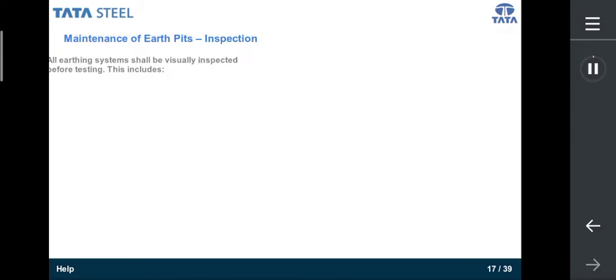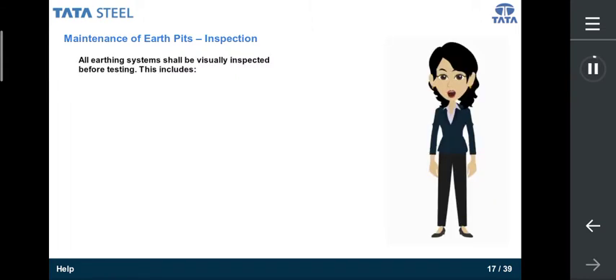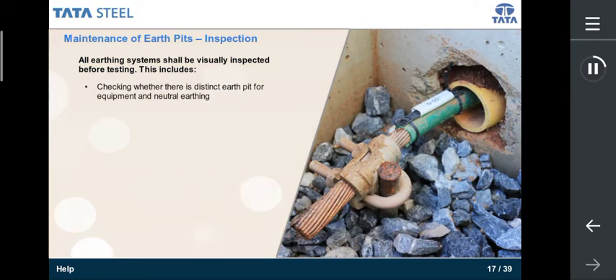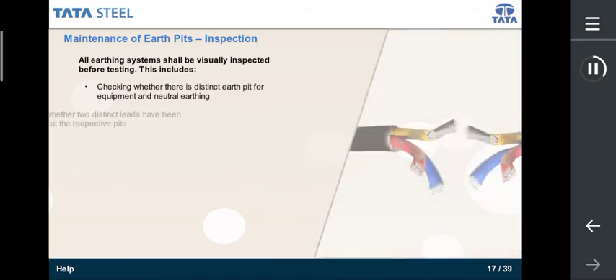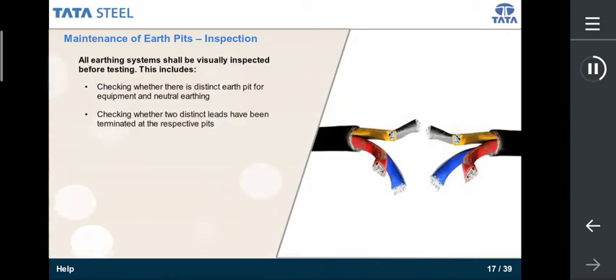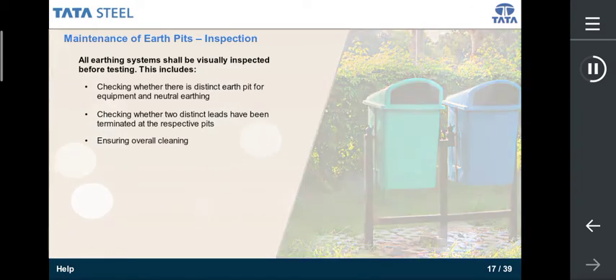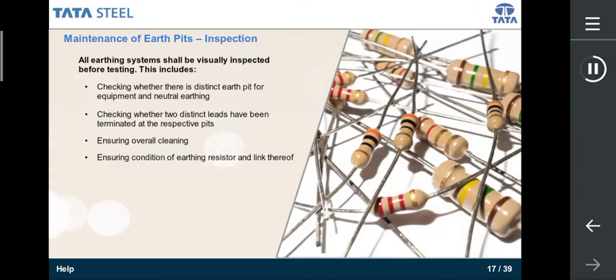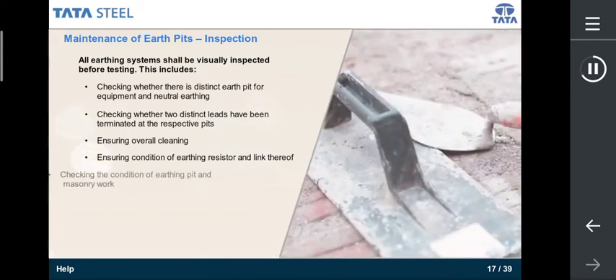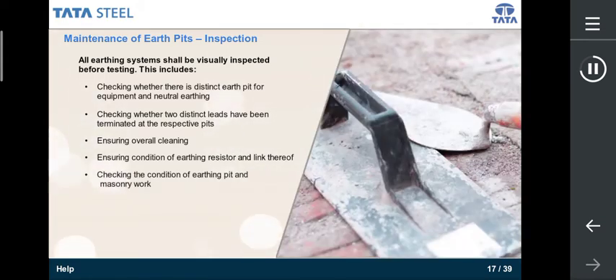All earthing systems shall be visually inspected before testing. This includes checking whether there is a distinct earth pit for equipment and neutral earthing, checking whether two distinct leads have been terminated at the respective pits, ensuring overall cleaning, ensuring condition of earthing resistor and link thereof, checking the condition of earthing pit and masonry work, checking electrodes connection and their rigidity, and the condition of earth electrodes above ground level.